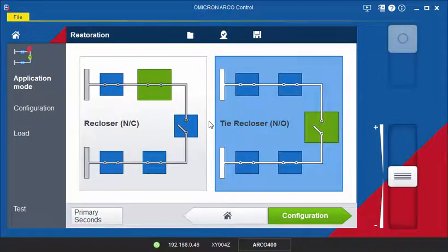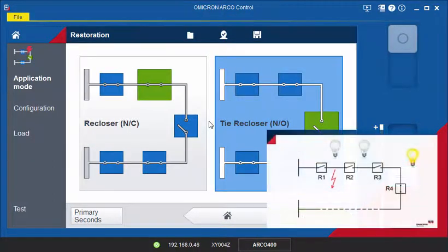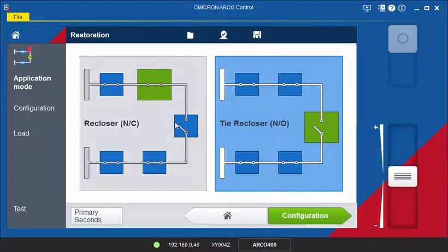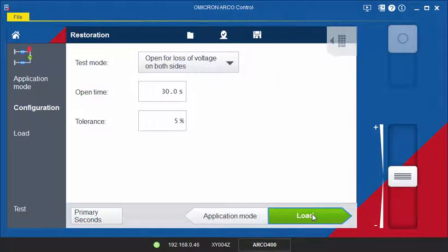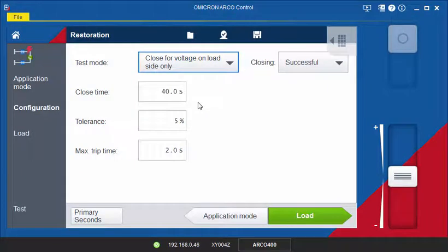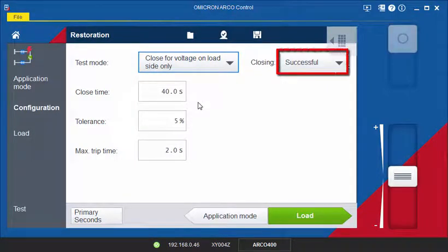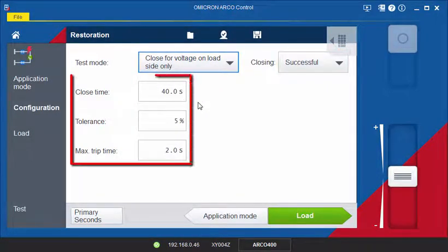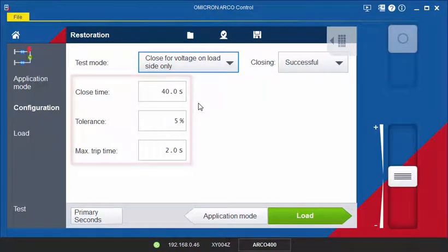The next step in our example is the reclosing of R3. R3 detects a voltage on the load side and then closes. You can test this in the application mode Re-Closer with Close for Voltage on Load Side Only. Select Successful Closing. Then, specify the other parameters as shown before.